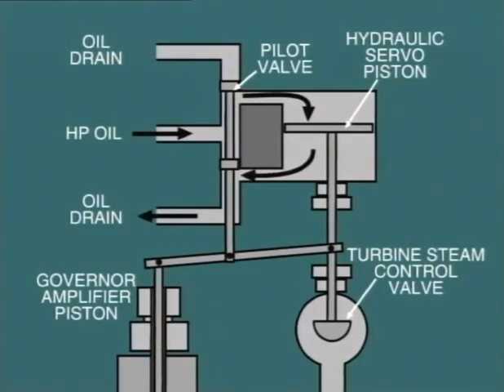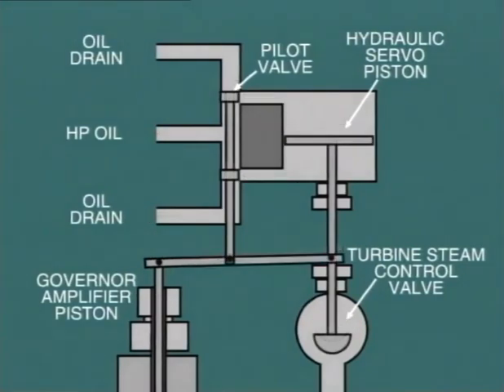At the same time, it will allow oil below the piston to pass to the oil drain. In response to this, the piston will be forced downwards, partially closing the control valve. This movement downward also moves the operating lever, and this moves the pilot valve downward, closing off the servo cylinder, which is now in a new position.